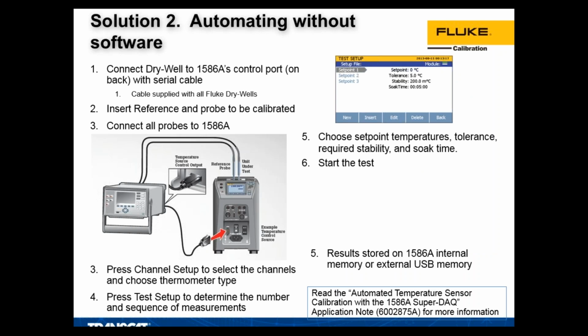So how do I set this up? First, I connect the dry well to the 1586A through the serial connection, using the regular RS-232 cable that comes with the unit. That's one difference from the previous method, where I needed a special cable to automate with the 754. This one comes right out of the box. I insert the probes, connect them to the 1586A, and start pressing the buttons on the front panel.